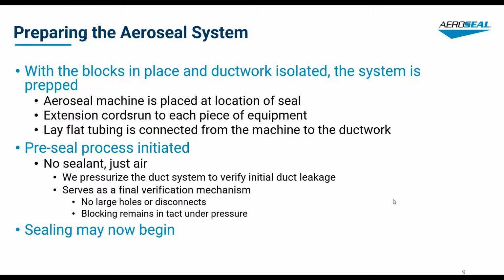This step is a lot of times how we'll find that there are big mechanical repairs that need to be done or fixed. We'll hook up and get a pretty good feeling of, hey, it's this size duct run, this much linear footage of duct, and we'll have a pretty good feel for around what it should be leaking, within reason. If it's something way off the charts, that's when we double down and double check, going back through the sealing to make sure we're not seeing or hearing air come out of somewhere. If we do find it, then we'll go ahead and fix it.